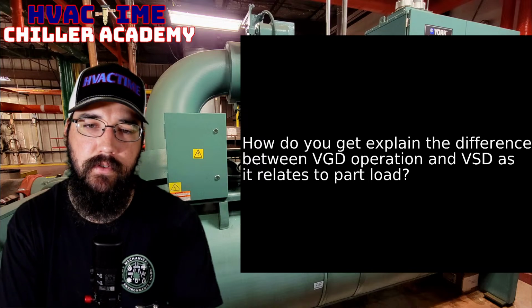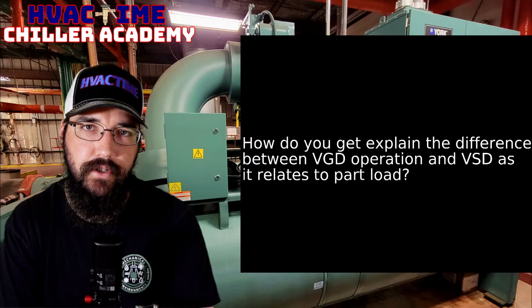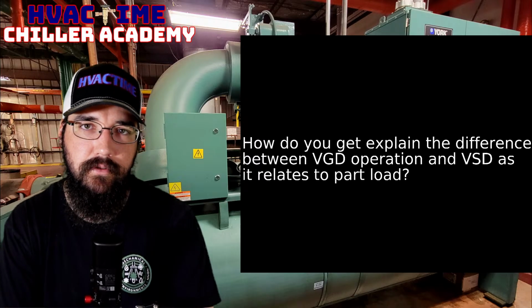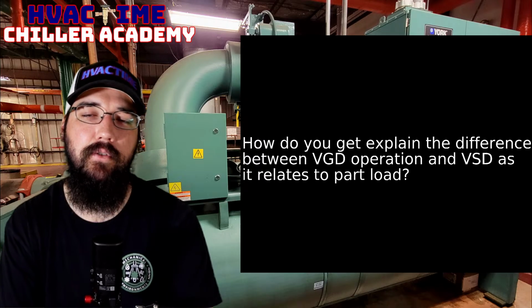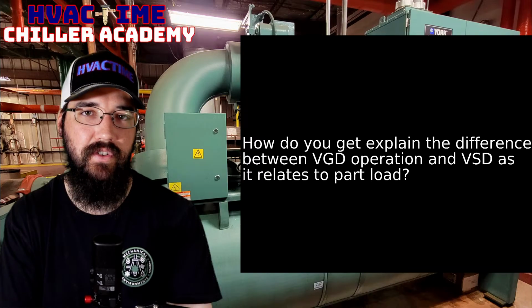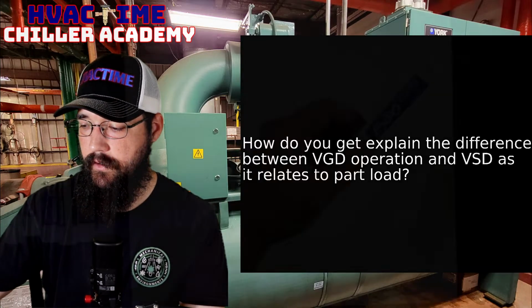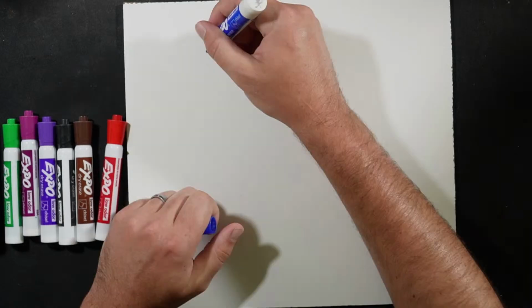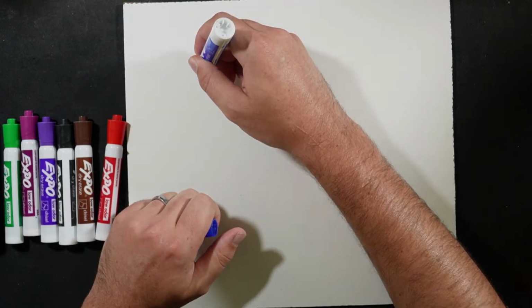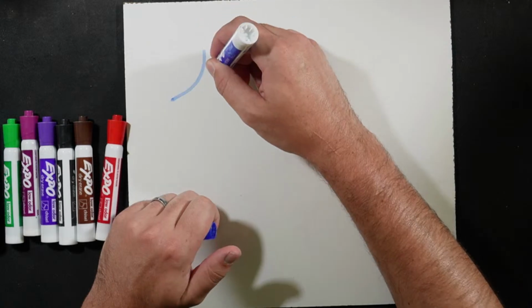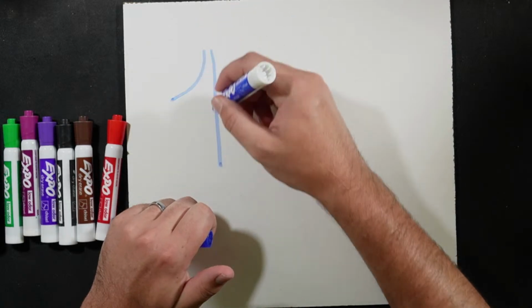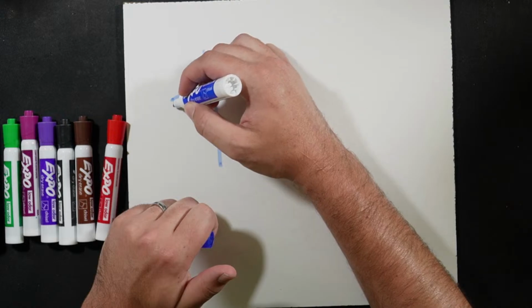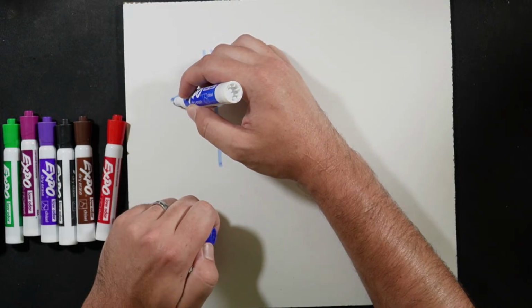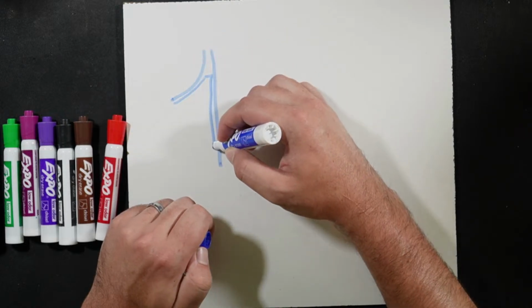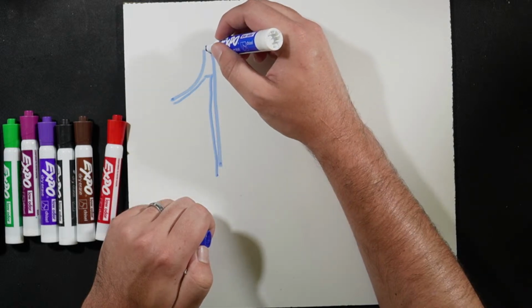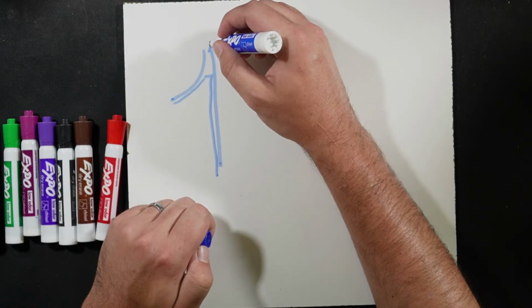To separate the two real quick, your VGD is a variable geometry diffuser that is in the diffuser section coming out of the compressor. So let's look at that real quick. Inside of the compressor here, we have our back wall of the rotor housing, we have the front. This is your impeller sitting inside of here. That's going to come across, come down this back wall. Right in here is your diffuser.